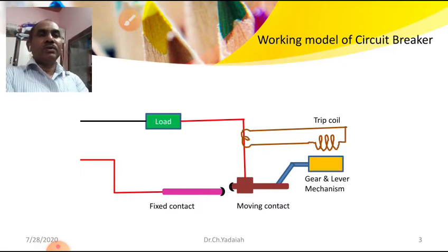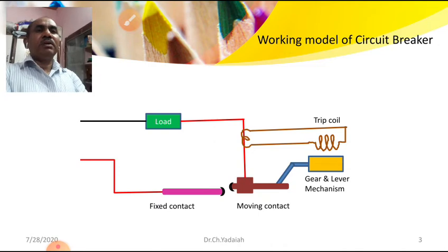Once the small air gap forms before elongation of the moving contact, that gap creates a large voltage between the two electrodes. That voltage may break the dielectric strength of whatever media is between the two contacts, and if the dielectric strength fails, then that media becomes an ionized path. The ionized gas is nothing but a flexible conductor through which electrons will try to flow.